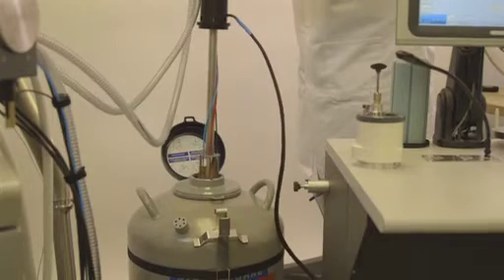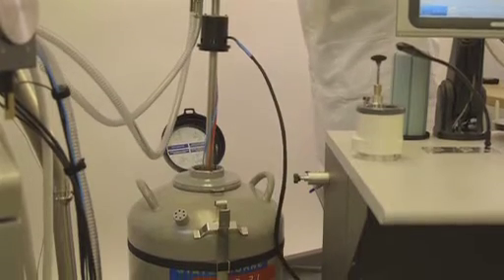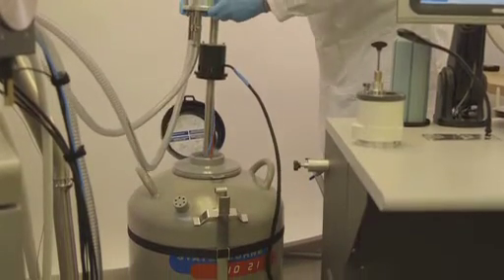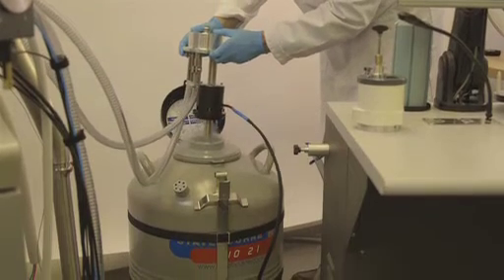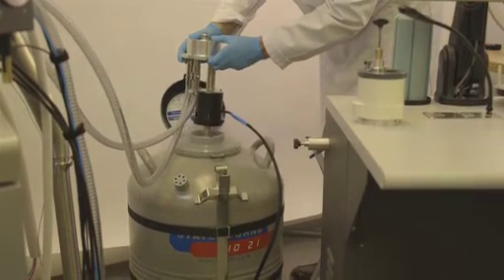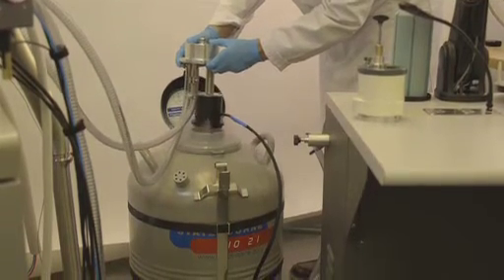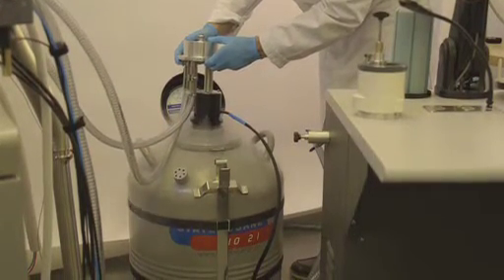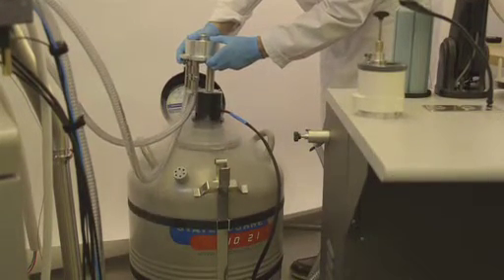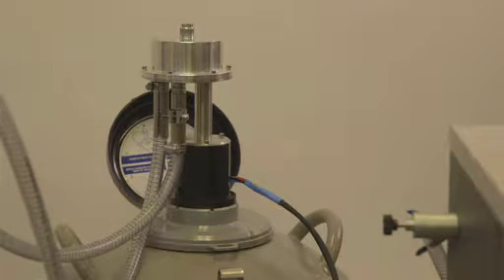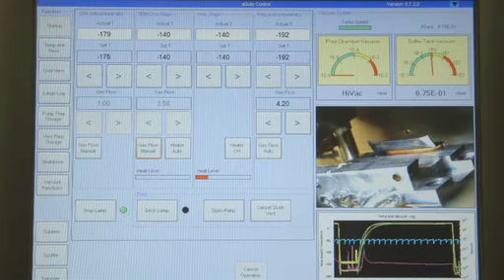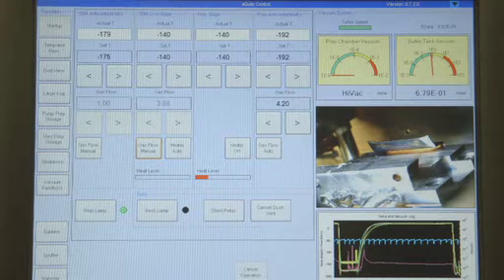Once the required vacuum is reached, the heat exchanger is lowered into the liquid nitrogen-filled dewar and cool-down started. Cooled nitrogen gas is used to cool both the microscope and the preparation chamber cold stages, plus all the cold traps.